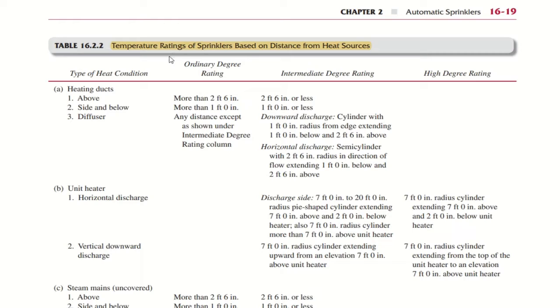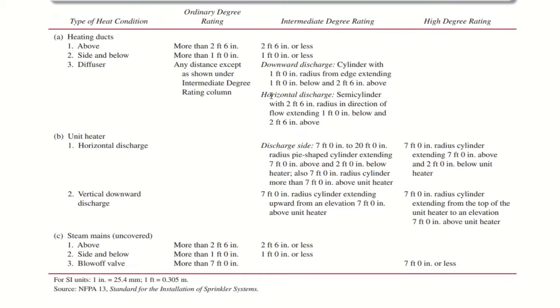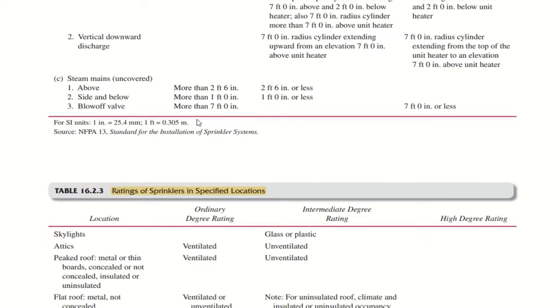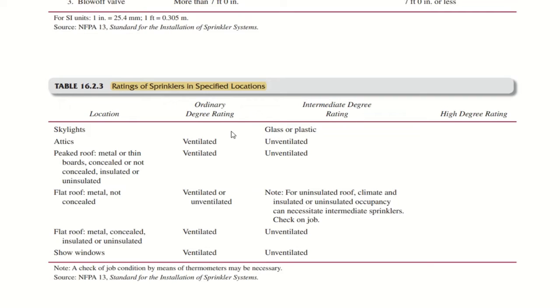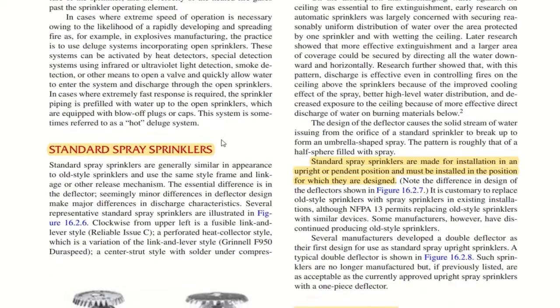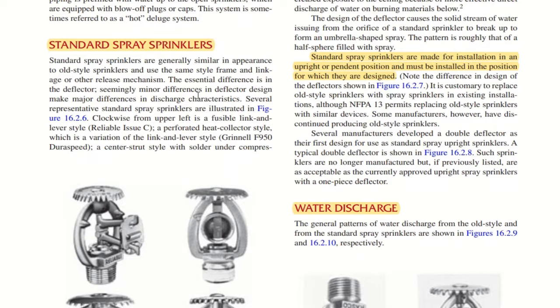Here you have one more table, temperature ratings of sprinklers based on distance from heat sources. You need to go through these temperature ratings also. Just make a note about this as well. Rating of sprinklers in specified locations. For example, you have skylights, so intermediate degree rating you need to consider. Skylights, glass or plastic, you know, type of material to be used. So you have basically standard spray sprinklers.